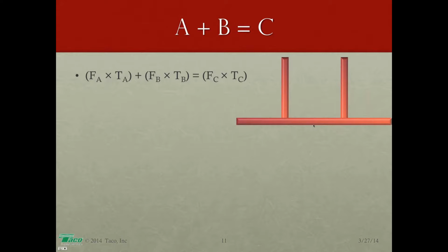This is a simple three-way mixing formula, all right? The flow and temperature in the common piping is A. Flow and temperature in the boiler supply is B. And then flow and temperature in the header supply is C. So I'm mixing my flow and temperature in A with the flow and temperature in B to get the desired flow and temperature in C. F is flow, T is temperature. Let's fill in some blanks.